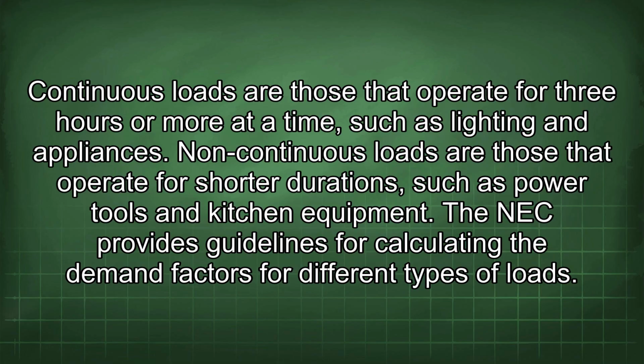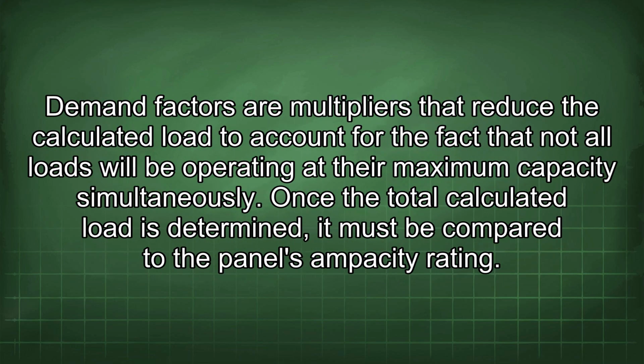Continuous loads are those that operate for 3 hours or more at a time, such as lighting and appliances. Non-continuous loads are those that operate for shorter durations, such as power tools and kitchen equipment. The NEC provides guidelines for calculating the demand factors for different types of loads. Demand factors are multipliers that reduce the calculated load to account for the fact that not all loads will be operating at their maximum capacity simultaneously.